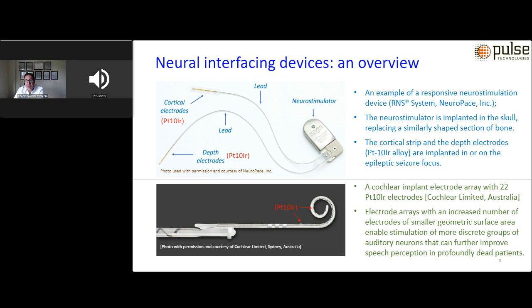For example, an example of a responsive neurostimulation device, which is implanted in the skull, replacing a similarly shaped section of the bone, and also the cortical strip and the depth electrodes that are platinum iridium alloys that are implanted in or on the epileptic seizure focus. Another example is the cochlear implant electrode array with 22 electrodes made out of platinum iridium, and with an increased number of electrodes of essentially smaller geometric surface area, stimulation of more discrete groups of auditory neurons is enabled that can improve speech perception in patients who are profoundly deaf.